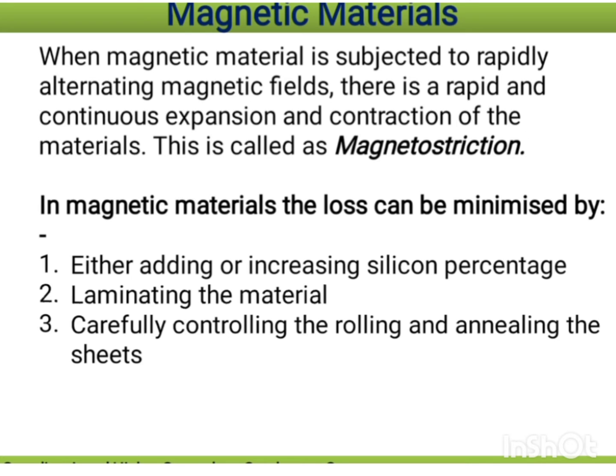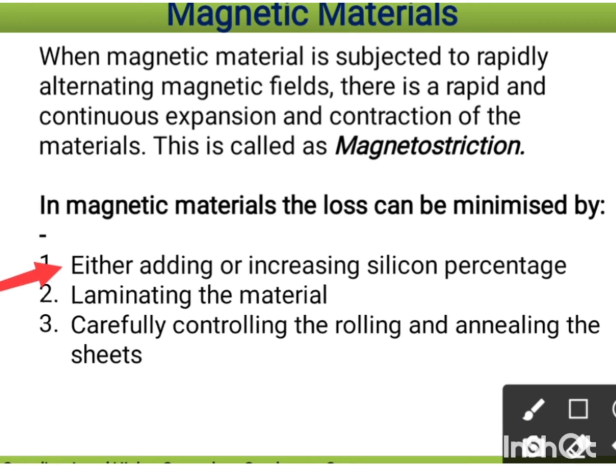Magnetic losses — including hysteresis loss and eddy current losses — can be minimized, though not completely eliminated. Methods include: first, adding or increasing the silicon percentage; second, laminating the material, which increases resistance and thereby reduces eddy currents; and third, carefully controlling the rolling and annealing of the sheet.